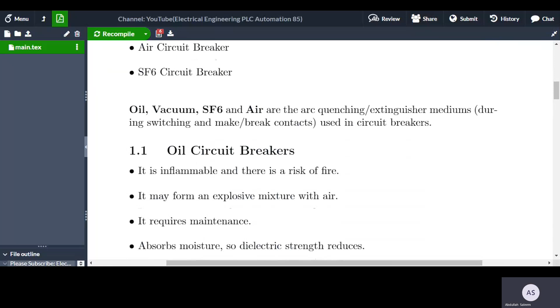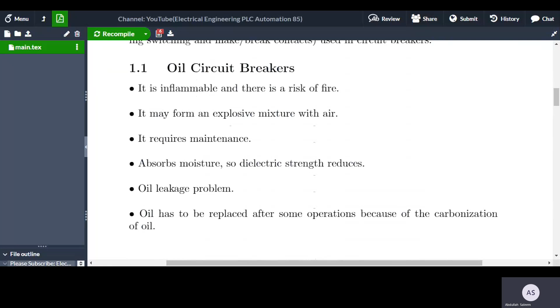It absorbs moisture, so dielectric strength decreases. So that is another limitation associated with oil circuit breaker. On the same way, oil leakage problem, oil has to be replaced after some operations because of the carbonization of oil. So maintenance is required in oil circuit breakers.